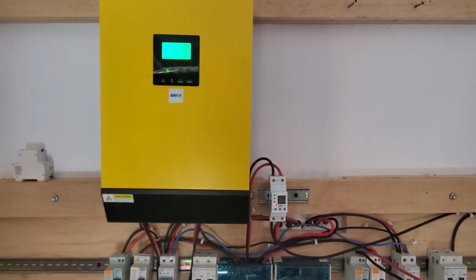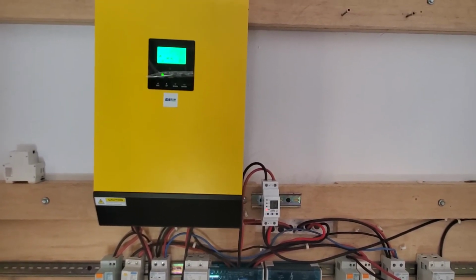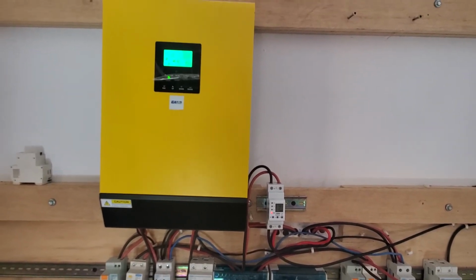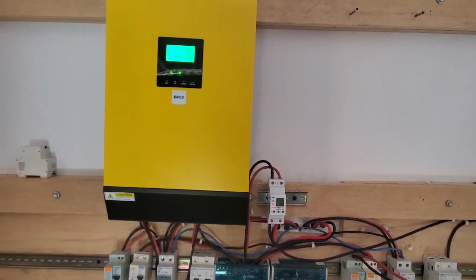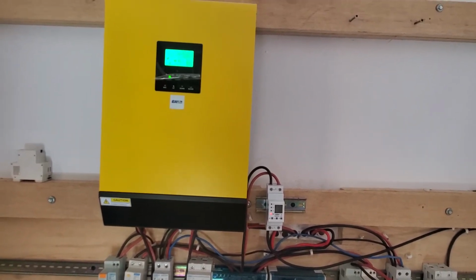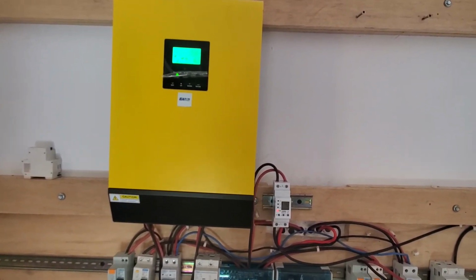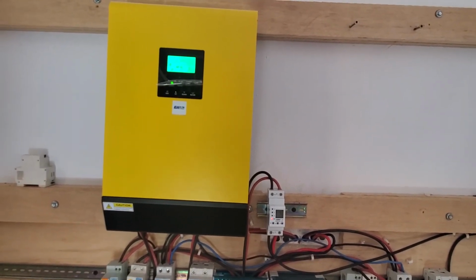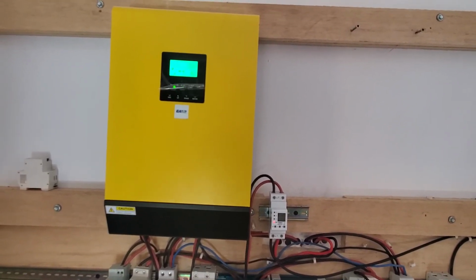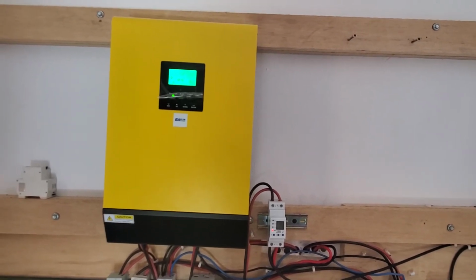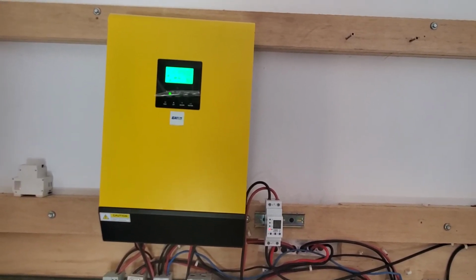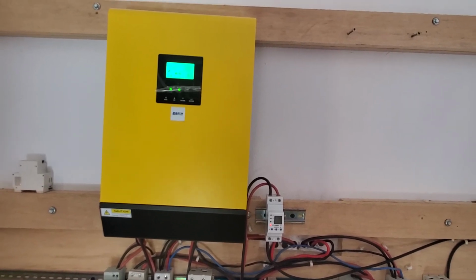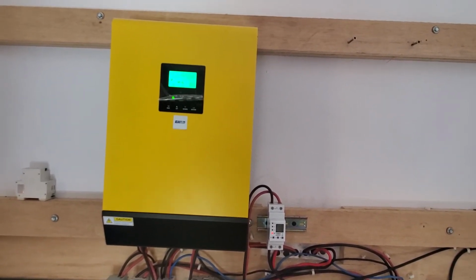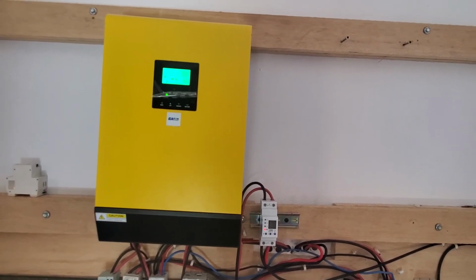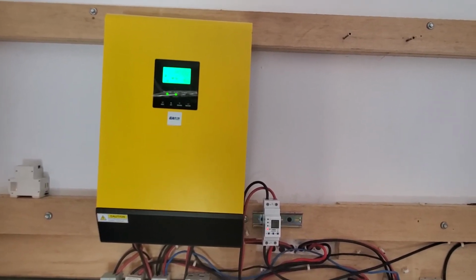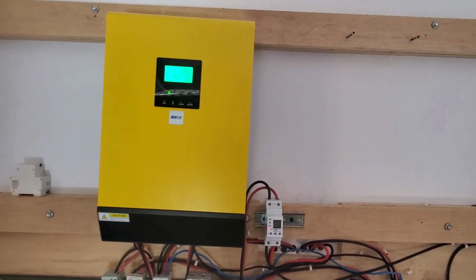Why my preference? Because this one has got about 20,000 charge cycles. What this means is that you can use it for over 54 years before replacing it. It also has something we call the DOD, or depth of discharge, of about 80%. As yet, research hasn't shown that if you go beyond 80%, it's going to have a significant effect on it.